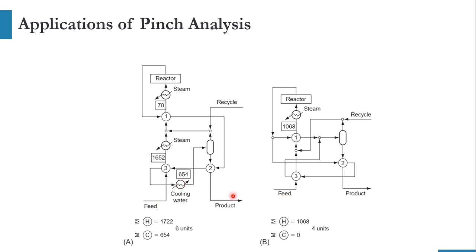Looking at a first system: feed goes to a heat exchanger requiring steam as utility, then to a reactor, then back through heat exchange with a cooling water requirement. The total heating requirement is 1722 kW, cooling requirement is 654 kW, and six units are required. In the improved system, the heating utility requirement has decreased to 1068 kW from 1722 kW, cooling water requirement is completely zero, and instead of two heat exchangers for steam there is only one. The system now uses only four units — saving two units and completely eliminating the cooling utility.